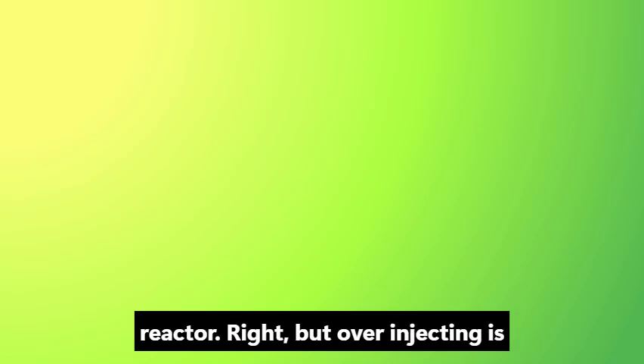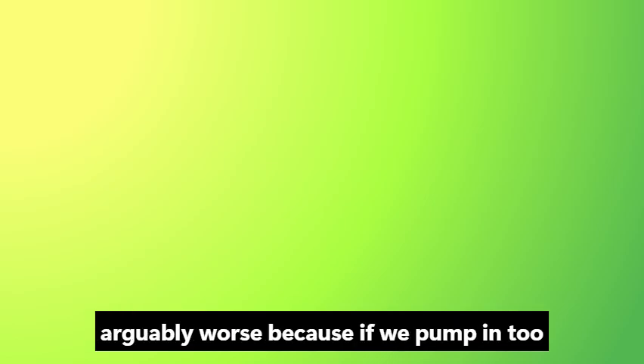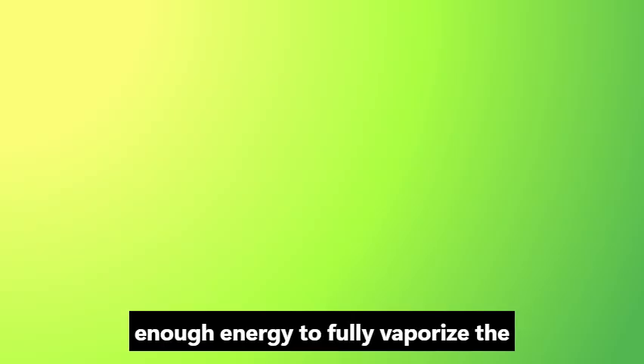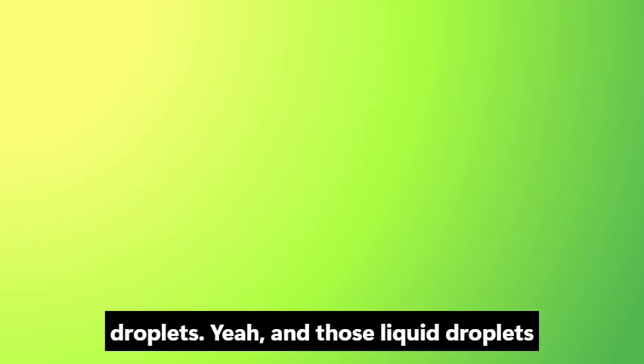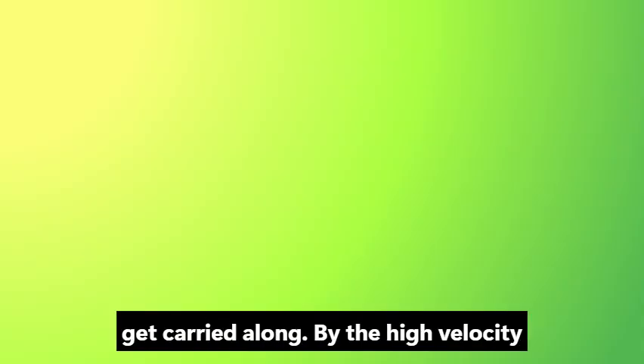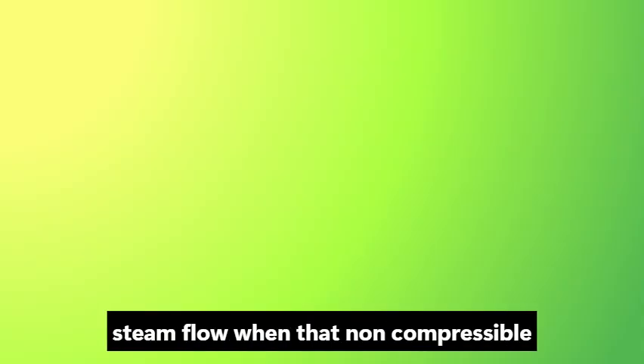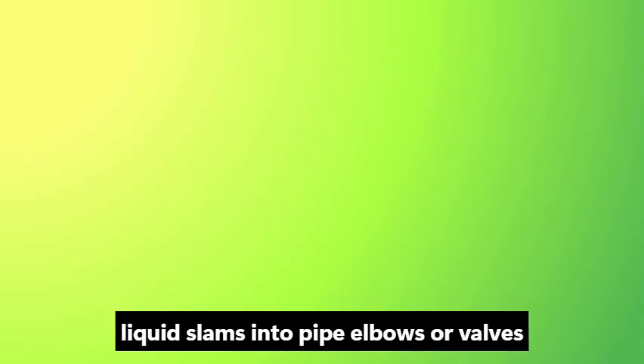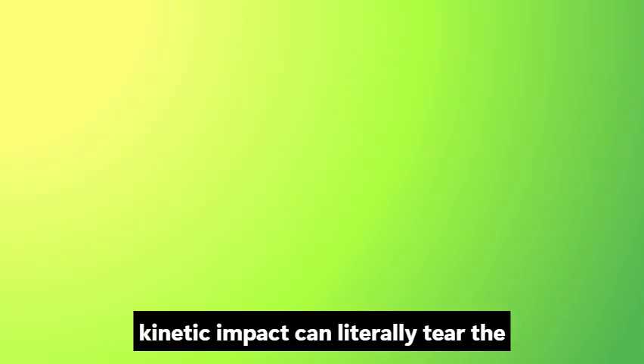Right. But overinjecting is arguably worse. Because if we pump in too much 50-degree water, the steam won't have enough energy to fully vaporize the droplets. Yeah, and those liquid droplets get carried along by the high-velocity steam flow. When that non-compressible liquid slams into pipe elbows or valves, you get water hammer. Exactly. The kinetic impact can literally tear the piping supports out of the concrete. Yeah. Or shatter the internal metallurgy.